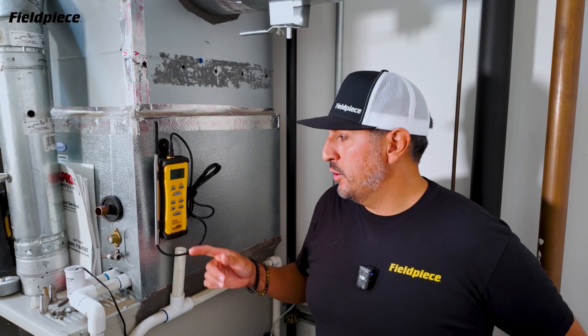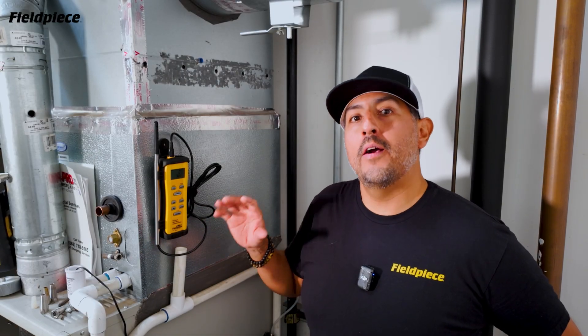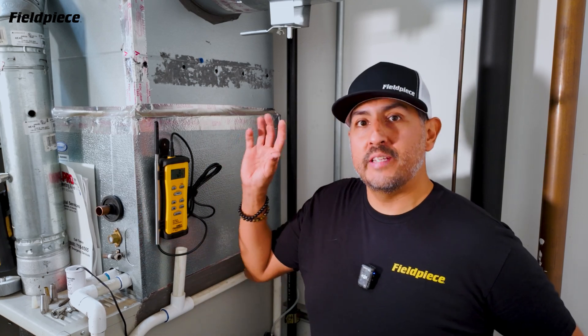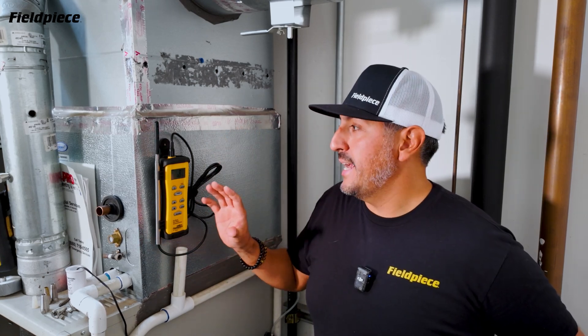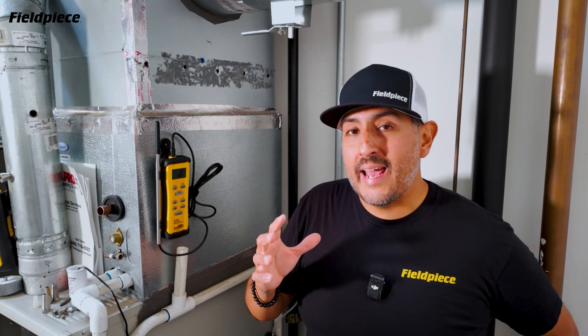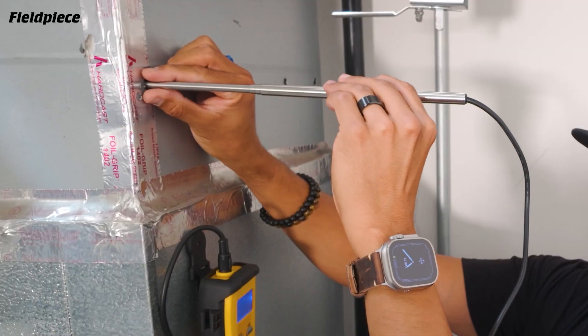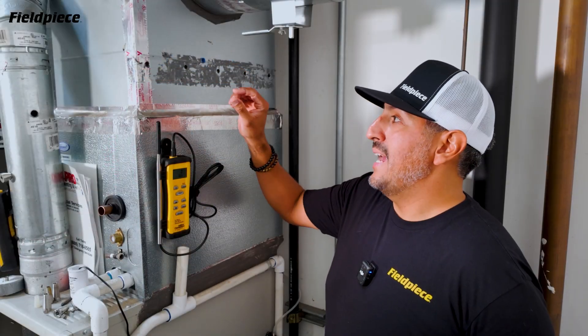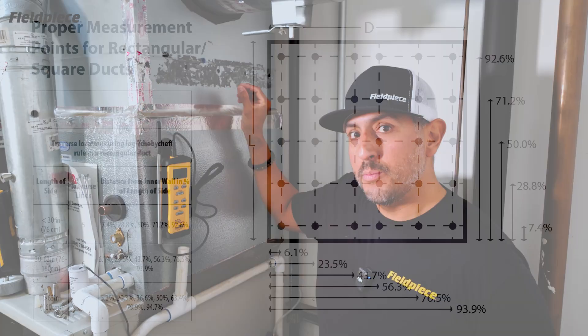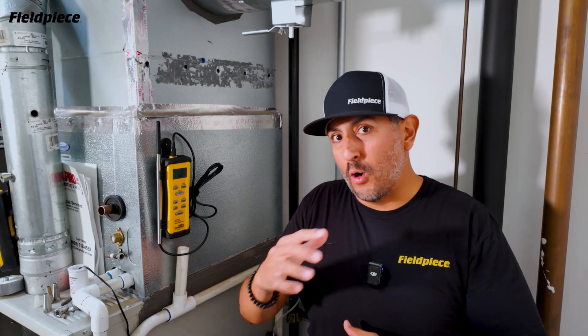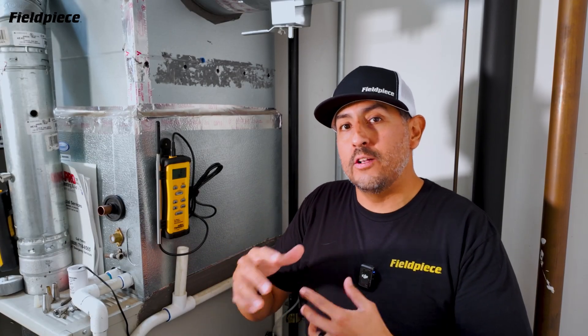The FieldPiece SCA2 is an induct hotwire anemometer. An anemometer is a tool that measures air velocity, and the SCA2 has an anemometer sensor — the hot wire — and another sensor to measure temperature. In order to calculate and measure CFM with the SCA2, we're going to perform a process called the duct traverse, which means we're going to take a bunch of air velocity measurements in the cross section of a duct, average those together, and then allow the tool to convert that air velocity into a CFM volume.